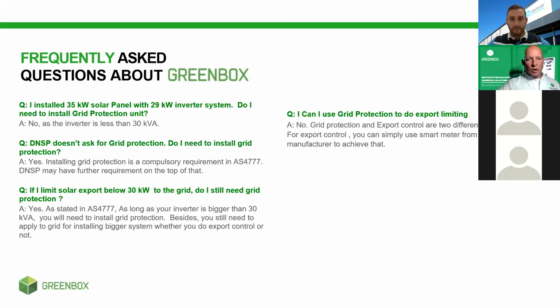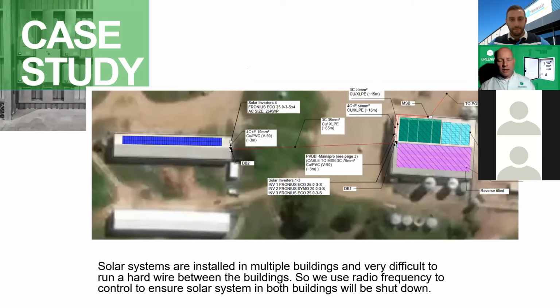All right, then we'll go to the next little bit of a case study here. Ideally, in the ideal world, we'd like to install a main grid protection board always near the main switch. I'll give you a heads up: some DNSPs actually require you to do it, not all of them, but some do. So be careful, make sure you get the right information. If it's not required, that's easy, you can then put your board further away or wherever it's more convenient for you to put your grid protection device.